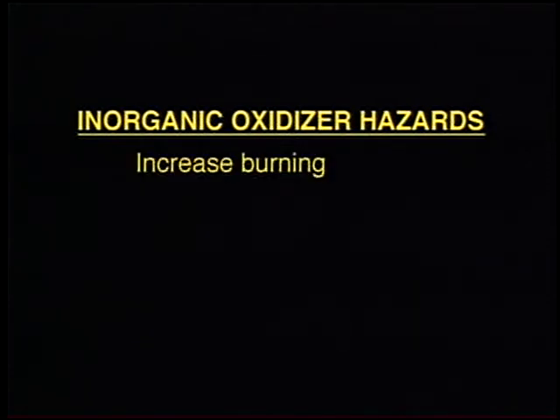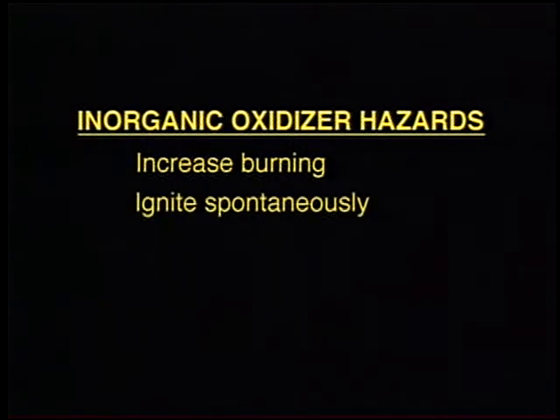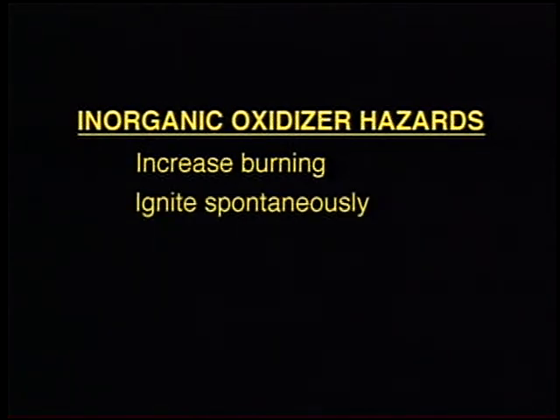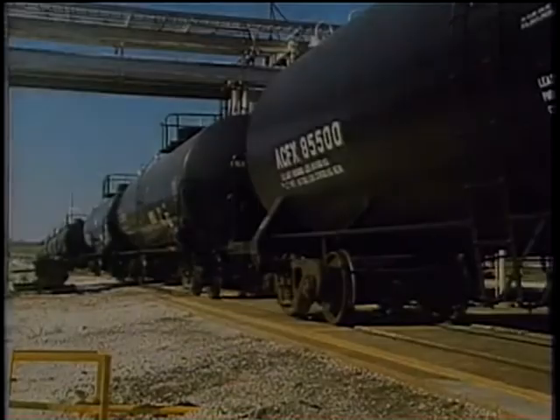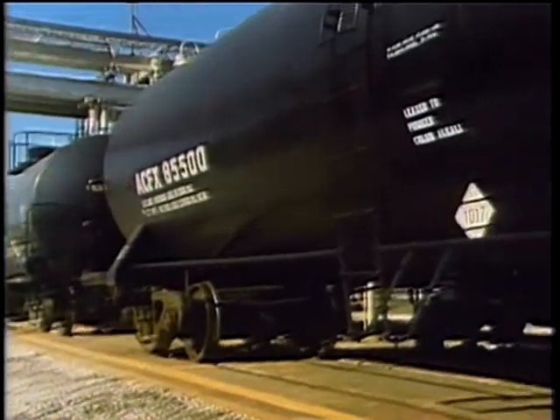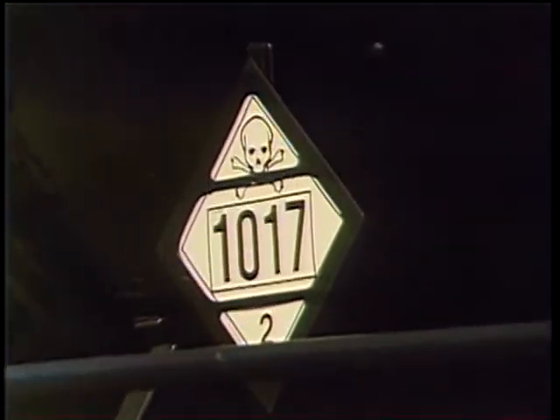The program also covers firefighting tactics and response procedures for leaks and spills. Inorganic oxidizers present one or more of four distinct hazards: they may increase the burning rate of combustible materials, cause spontaneous ignition of combustible materials, decompose and release hazardous gases, or undergo self-sustained decomposition and explode.